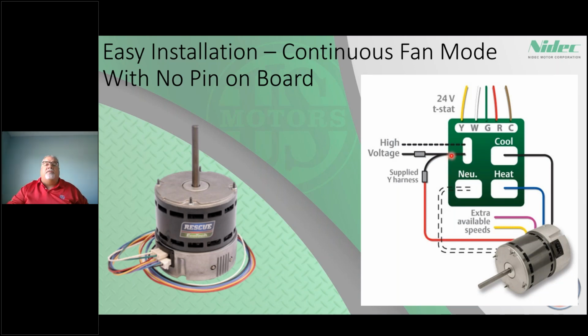So when I close that panel, this motor is going to be energized on the red lead, ramping up to 600 RPM, just running, mixing the air, getting rid of stratification, making sure indoor air quality is maintained. When a call for heat or cool comes, I've got a red lead and a black lead both energized at the same time. If you've ever had two leads touch at the same time, you know the motor starts to scream, whine, and eventually you let the smoke out, because you've basically given the motor two 115 signals, and it doesn't like that. So this motor says, I'm getting two signals, I'm going to ramp up to that higher speed. Once the call for cool goes away, it ramps back down and continues to run at 600 until it gets another signal. It's really a smart control that tells the motor exactly how to operate.